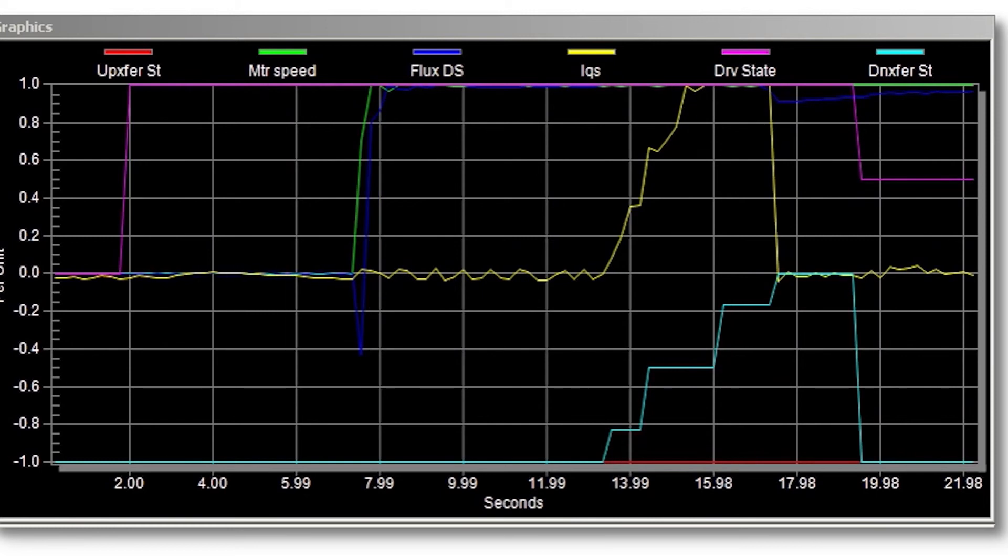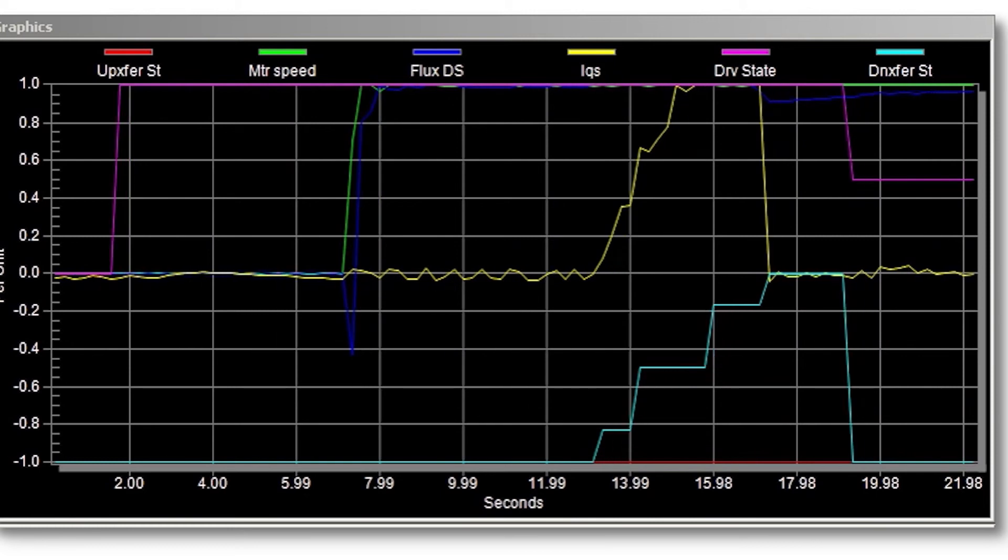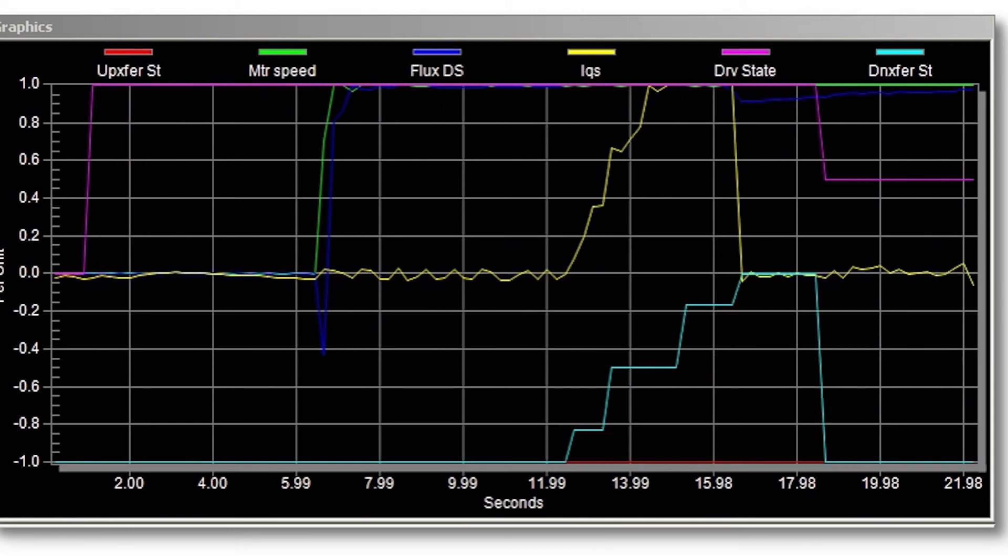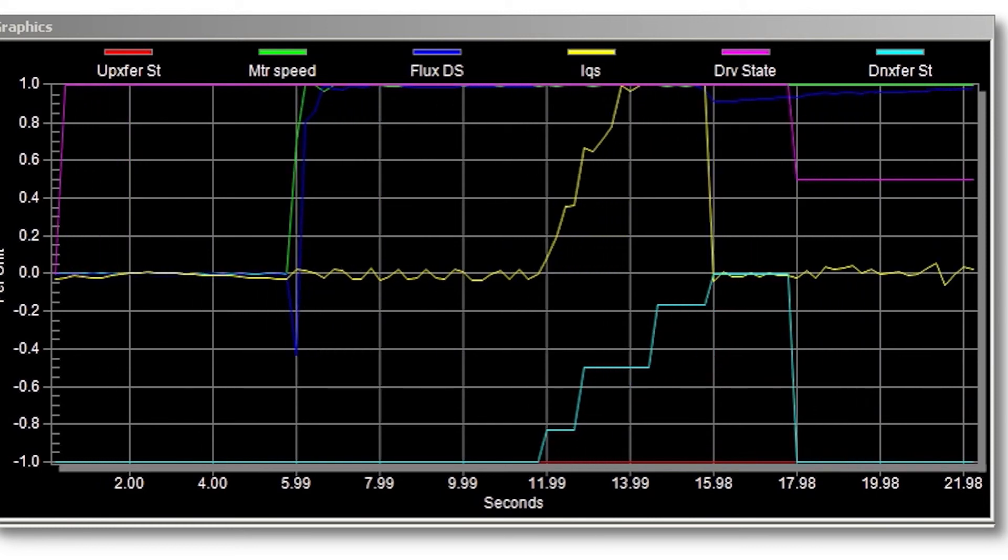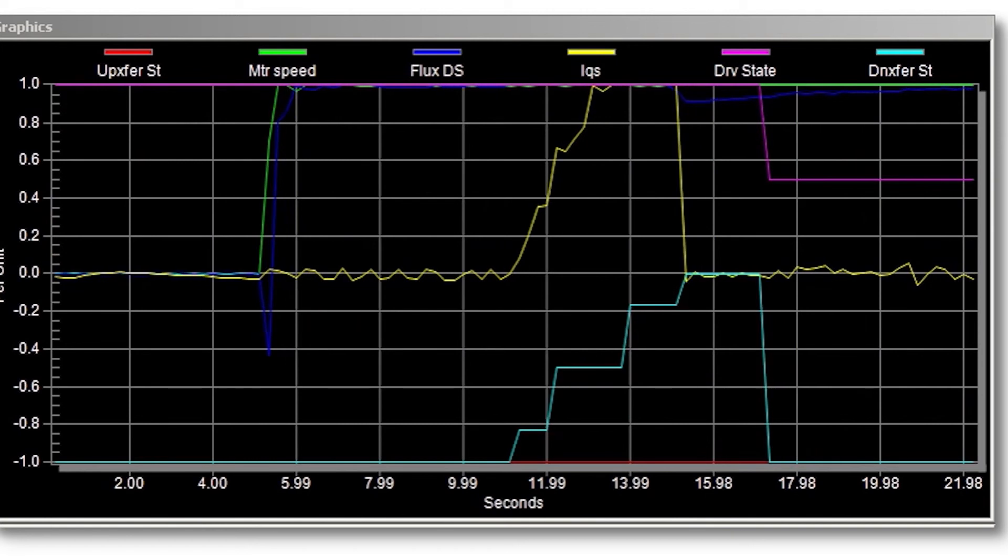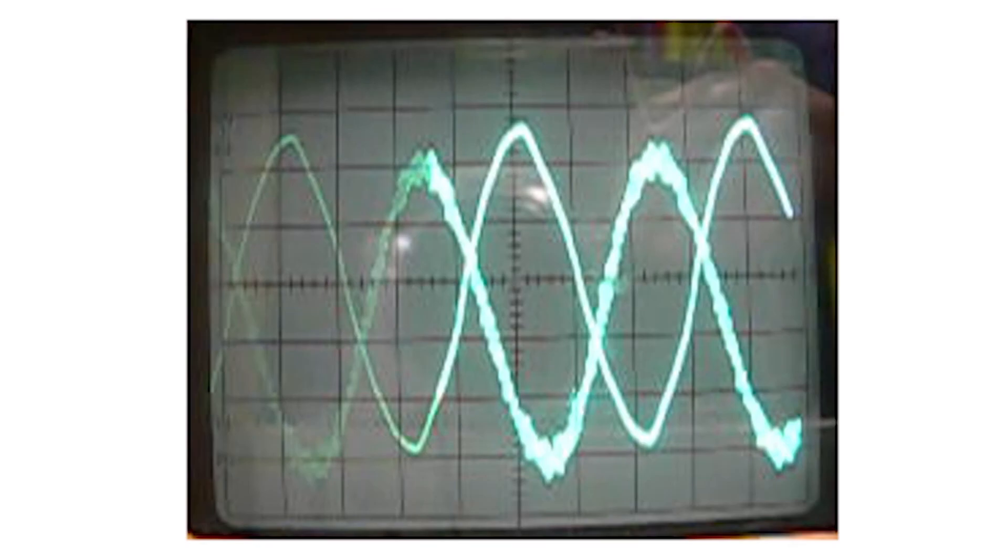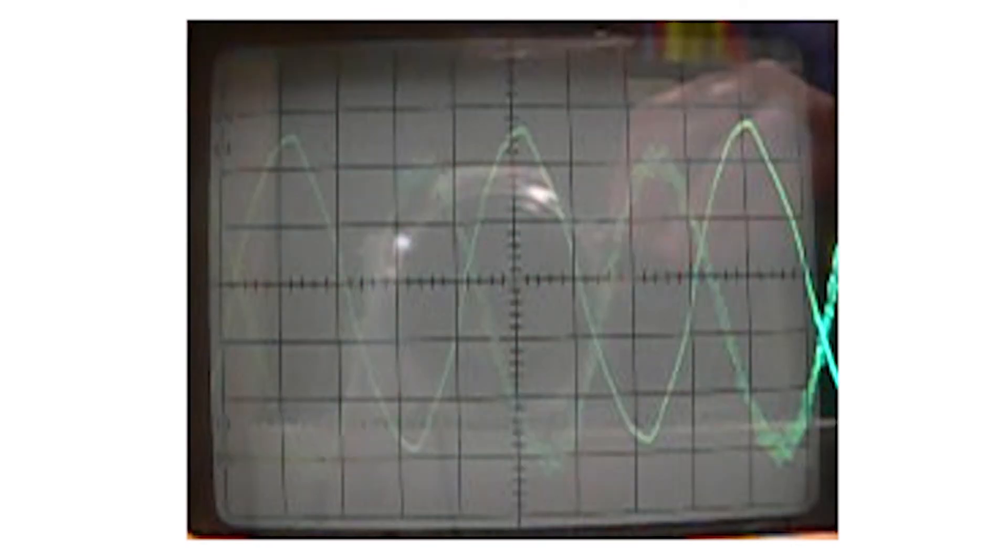The down transfer request is then removed and the VFD is in control of the motor. The same test is repeated while monitoring the motor. The scope trace will show the output drive voltage and the line voltage feedback at the same time.